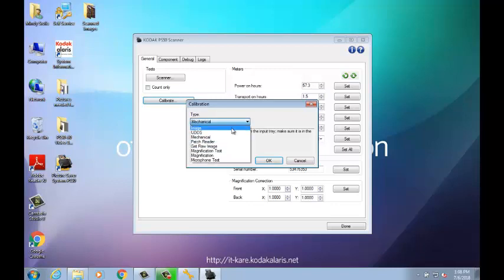Lastly, there is an image calibration, where the scanner takes 2 readings, one with the lights off and one with the lights on, to create normalization values for the upper and lower camera calibration tables. Each calibration requires the calibration target paper. The target paper is scanner model specific, therefore it cannot be used interchangeably between different scanner models.